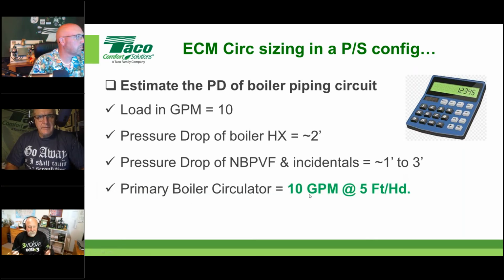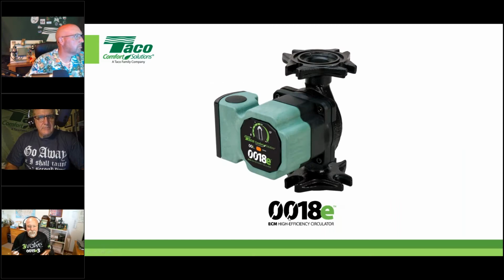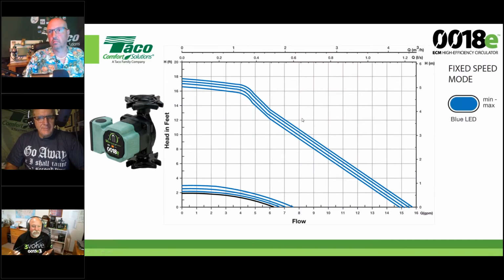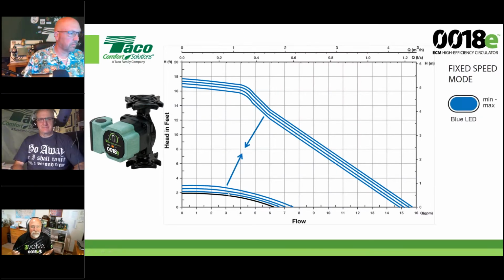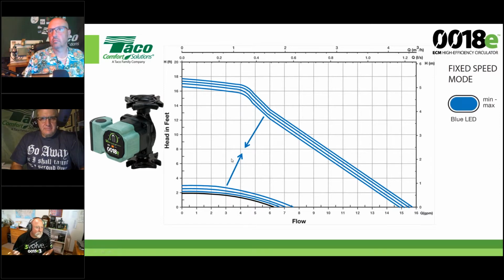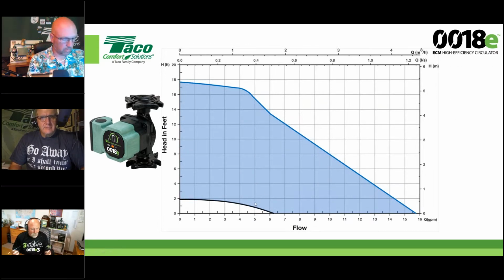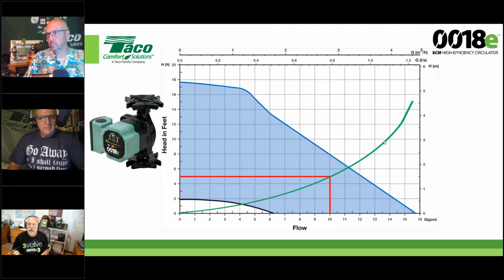Okay, so let's put it all together. I need a pump at 10 GPM at 5 feet of head. I introduce you to the 0018E. This is the coolest little pump that's known to man right now in this little category of ECM offerings, okay? Notice that we can run it anywhere between 4 watts and 44 watts, and that's what makes it real handy for what we need to do in this particular case. This shaded area represents anywhere between the 4 and 44 watts. So let's put our criteria in there at 10 gallons a minute and 5 feet of head. We find our operating point based on the resistance that we estimated of the system, and there's our operating point right there. So that would give us exactly what we wanted.